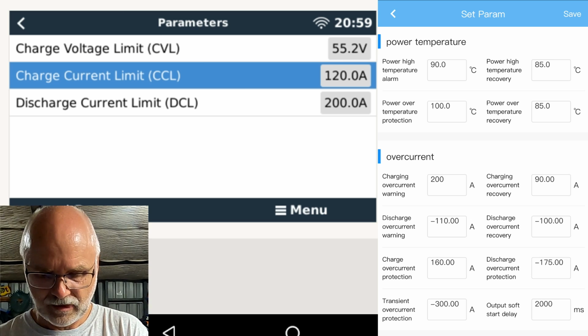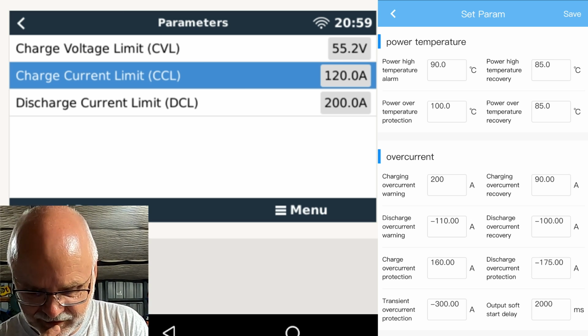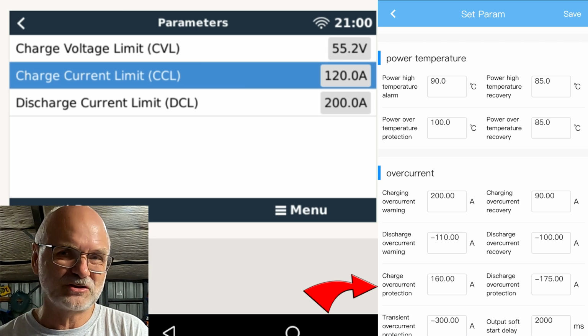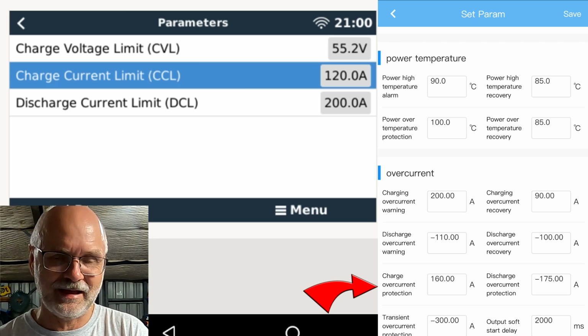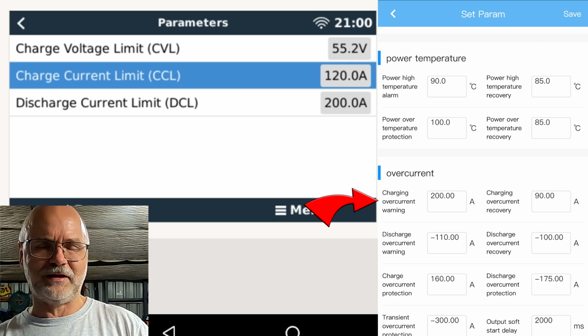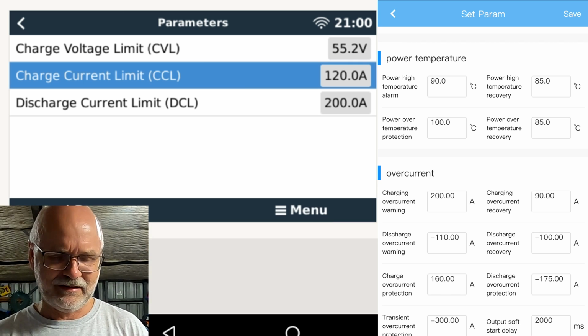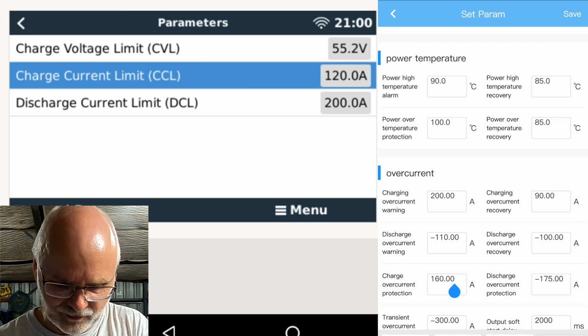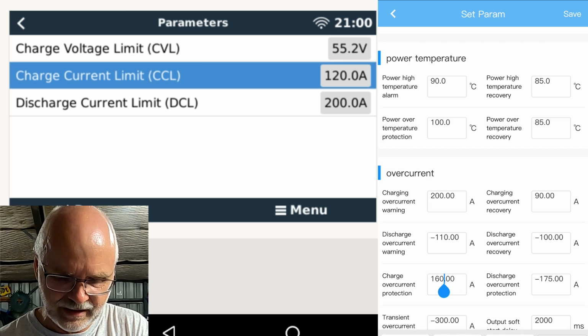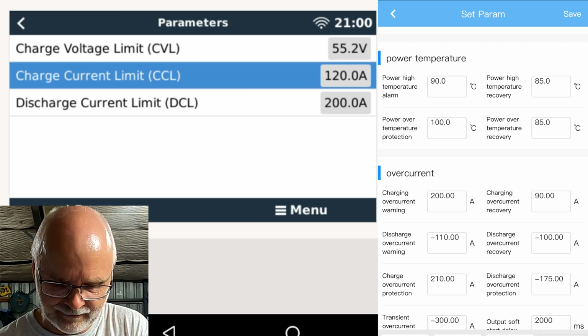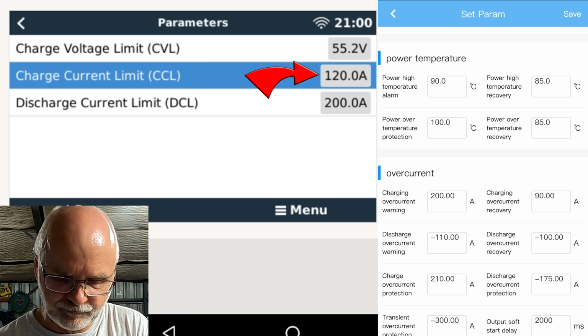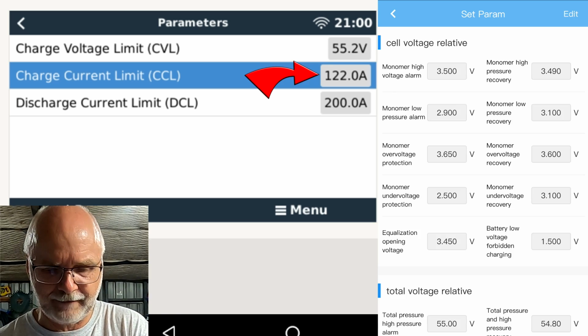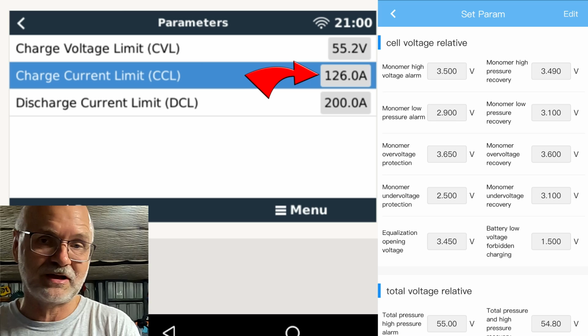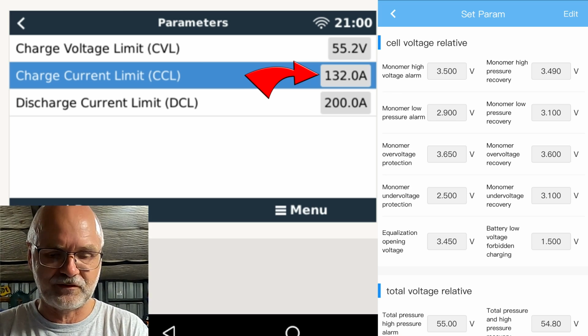Oh no. Maybe one of my other parameters. See, now because our charge overcurrent protection is set on 160 amps, but we have set the warning to 200 amps, which doesn't make sense. It doesn't save the parameters then, because this is not making any sense. So we need to set this one equal or higher than the actual warning. So I'll set this one to 210 amps. So we can save both parameters if we get a success. Yep. We can see now the charging current limit is increasing in the Victron system.